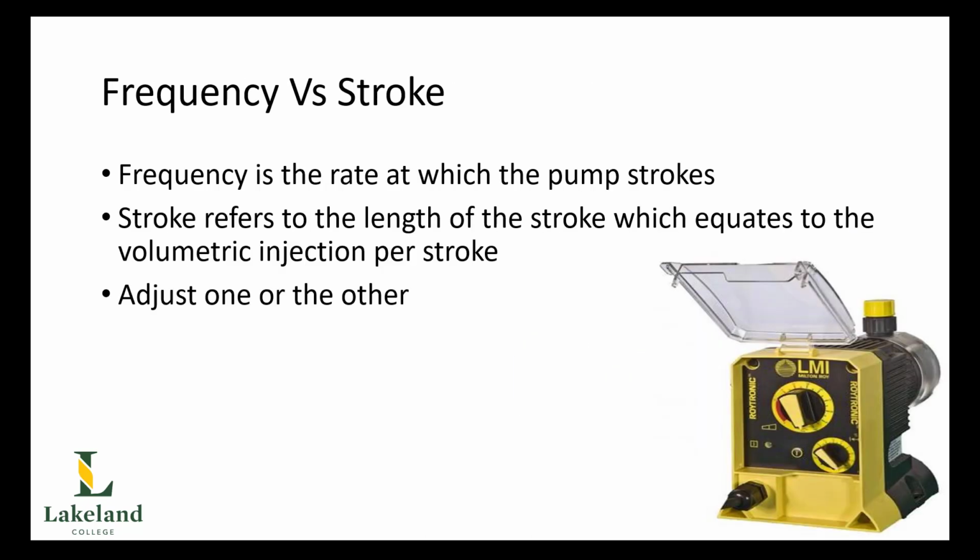Now, the frequency is simply the rate at which the pump strokes, as the definition of frequency is the number of cycles per second. So therefore, if we increase frequency, the pump will pump faster. When you listen to these things, they sound clicky, i.e. click, click, click, as the pump's moving along. If we dialed up the frequency, those clicks are going to be a lot closer together. Click, click, click, click, click. As it moves up and up and up, it's pumping more chemical.